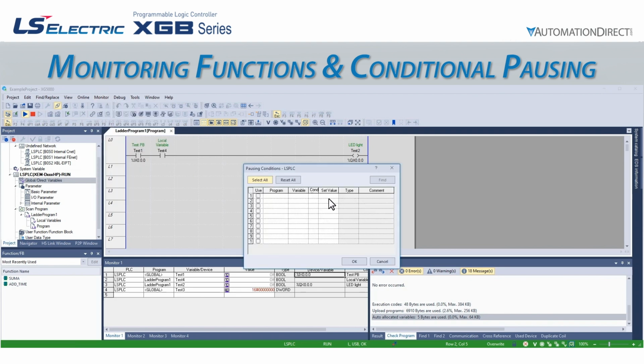To set conditions for pausing the monitoring, we go to the Monitor menu and select Pausing Conditions. This opens the Pausing Conditions pop-up window. In this window, we can set up various conditions that will pause the monitoring. These conditions will be compared between a selected variable and a preset value. There are several logic operators that may be used for the compare, and you can set multiple conditions with one or multiple variables.